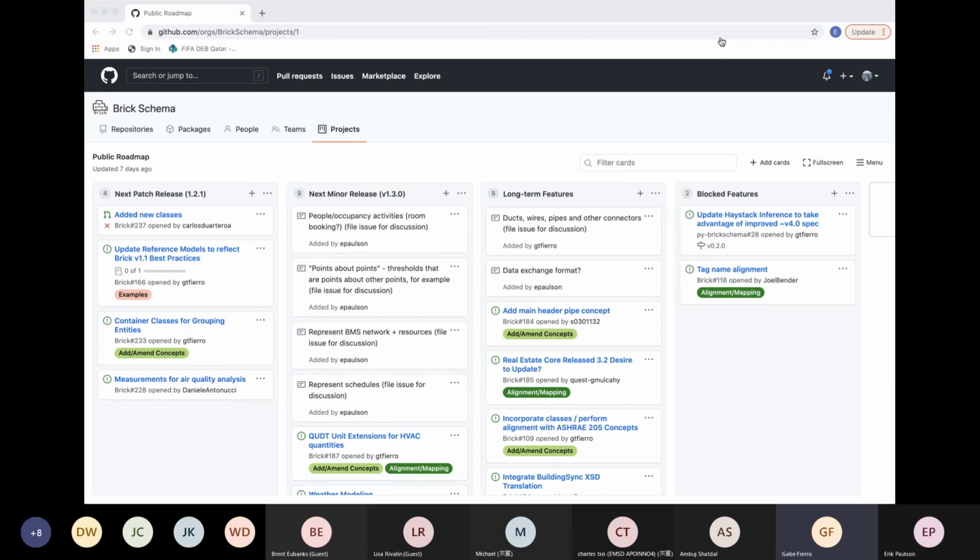Once it's possible to represent RDF data inside a BACnet object, that can represent Brick, that can hold 223, that can hold other ontologies. So there is both the standardization effort, with things like 223 and Brick, as those come off the ground, hopefully people start to include them. But there's also the technical mechanism by which that will be able to be included. And hopefully someday when you scrape your BACnet network, you can come away with some Brick annotations or some 223 annotations with it.